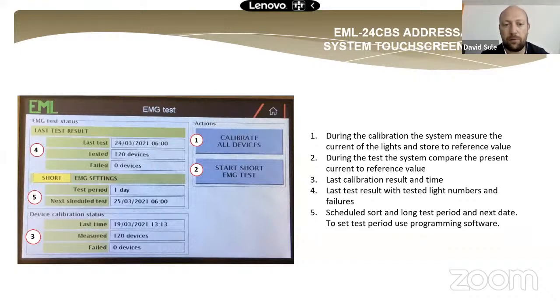And we have an option to start a short function test from the screen. One single click, all of the lights will turn to the emergency mode, and the panel will check one by one all of the addresses of the system. And after 2 minutes, the system will show what was the emergency test result.